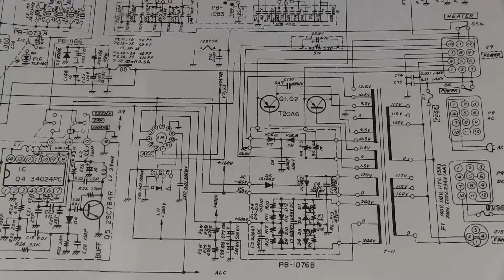160 volts DC plus. Now that's not good. That is showing a dead short on that DC volt line. You'll get it on AC, but you shouldn't get a dead short on the DC volt line. And let's check our minus 100. And you see we're in the kilohm range. But this one, plus 160 volts, is a dead short.